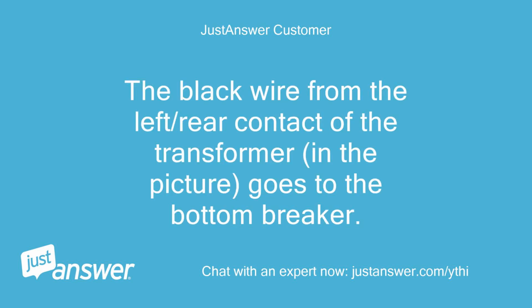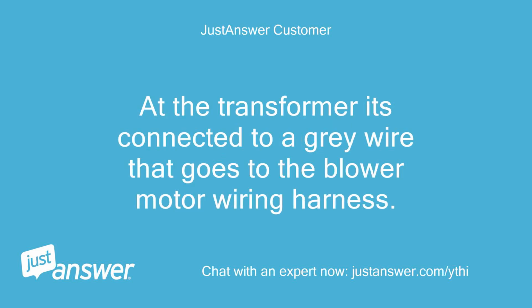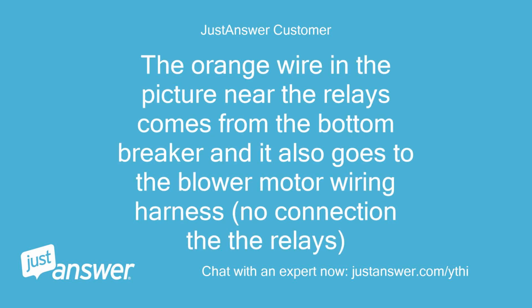The black wire from the left/rear contact of the transformer, in the picture, goes to the bottom breaker. At the transformer it's connected to a gray wire that goes to the blower motor wiring harness. The orange wire in the picture near the relays comes from the bottom breaker and it also goes to the blower motor wiring harness, no connection to the relays.